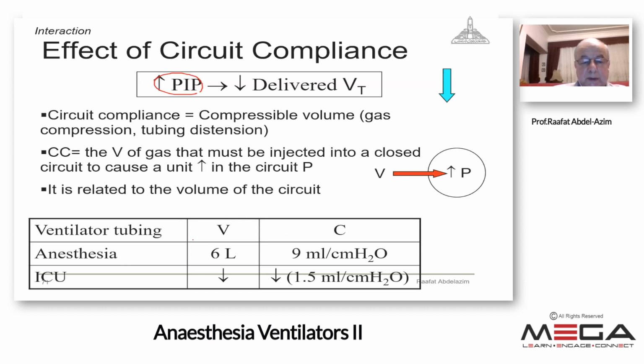The ventilator tubing is more compliant in the anesthesia breathing circuit, and it is less compliant in ICU because in most of the ICU patients, the peak pressure is high in asthmatics and COPD and other forms of respiratory failure. We usually meet patients with high pressure. So if the circuit is highly compliant, this will lead to too much loss. The circuit compliance in anesthesia ventilators may reach up to 9 milliliter per centimeter water. This means if the airway pressure is 10, there is 90 milliliter of volume lost. If it is 20, there is 180 milliliter of loss. This cannot be met in ICU ventilators because of the low compliance of the breathing circuit of the ICU ventilator.